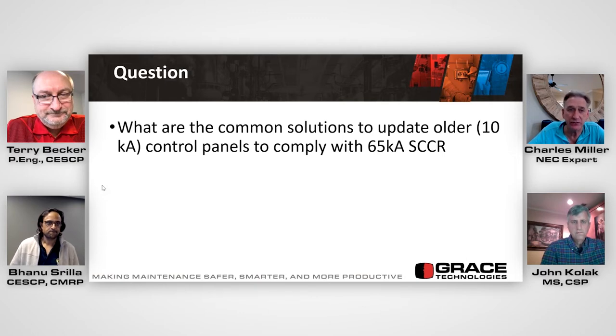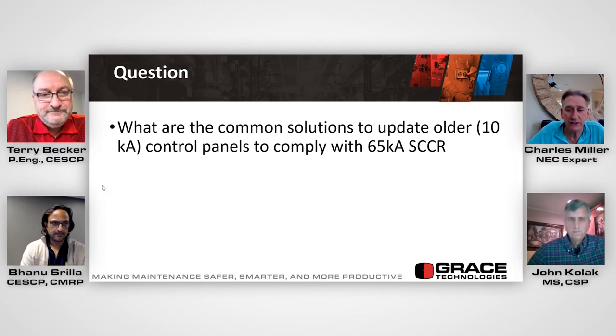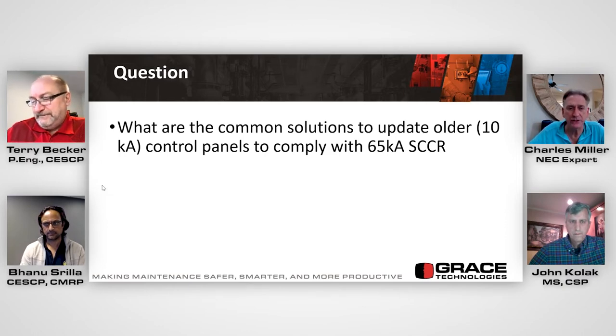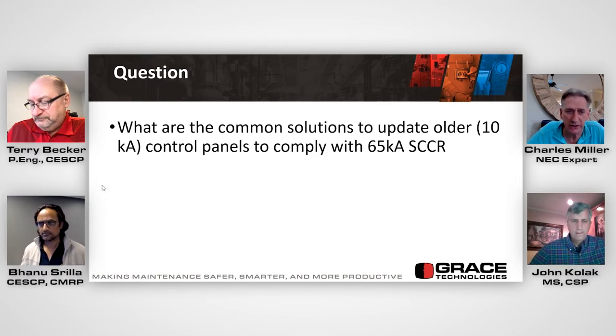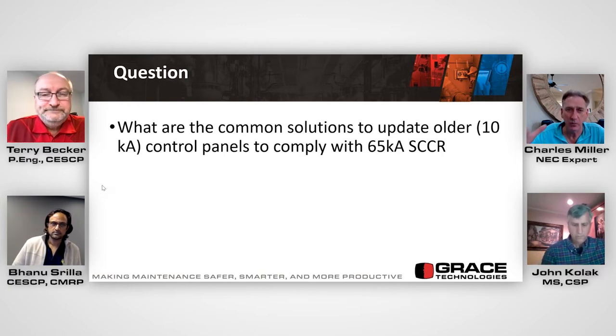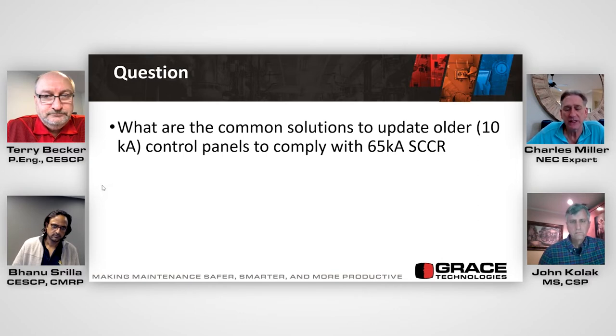There's equipment that has a series rating. I used to write and illustrate articles in Electrical Contractor magazine, and I did a whole series through Article 110. It took maybe three, four, or five years to go through three pages every month in that article in detail. I did cover this section on interrupting current and short circuit current, not the engineering side of it, but just what does the code say, what do we have to do if we're going to install this and meet the code, the NEC. That's where it came from.